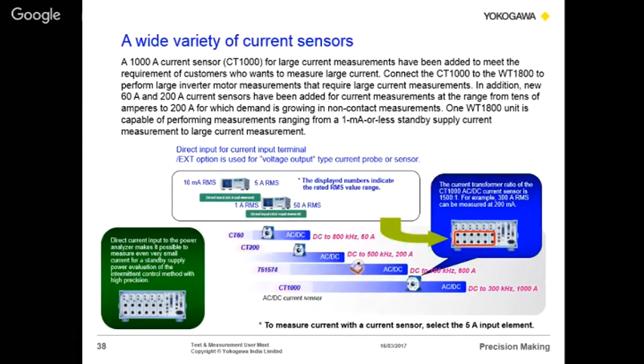Normally there are basically 2 types of current sensor. One measures the current and gives the output as a current. Another one measures the current and gives the output in terms of voltage. If you are directly connecting the current, meaning primary is current and secondary is also current, you can give it directly to the current terminal. If the CT or current sensor output is in millivolts, you can give it to the auxiliary sensor input. For example, your millivolt output will be like 10 millivolts per ampere. You have to set a ratio, like 10. If it measures 10 millivolts, it will be converted to equal 1 amp. So the equipment will automatically convert that ratio and give you the exact measurement of the current flowing through the circuit.